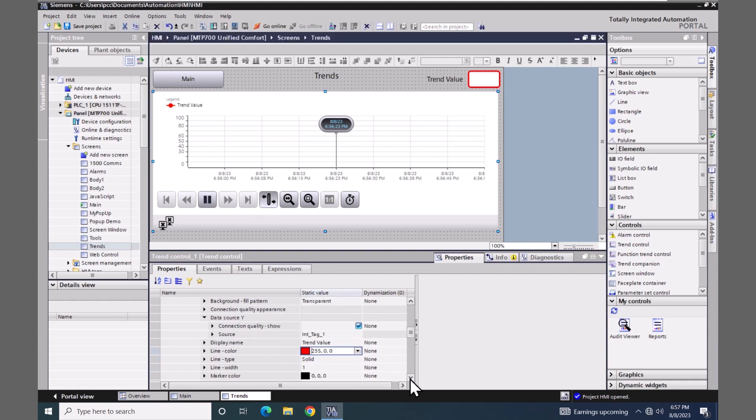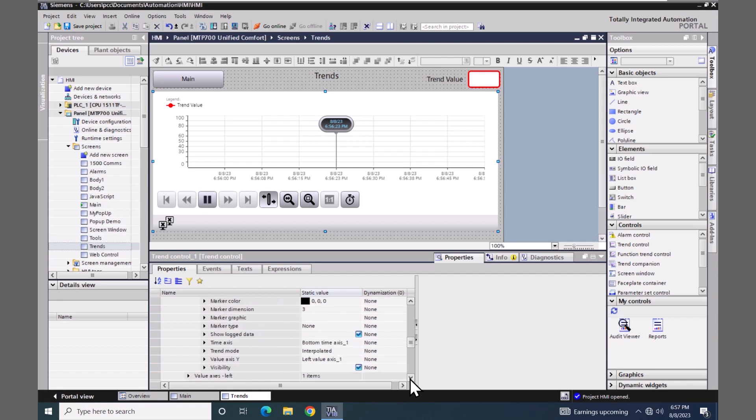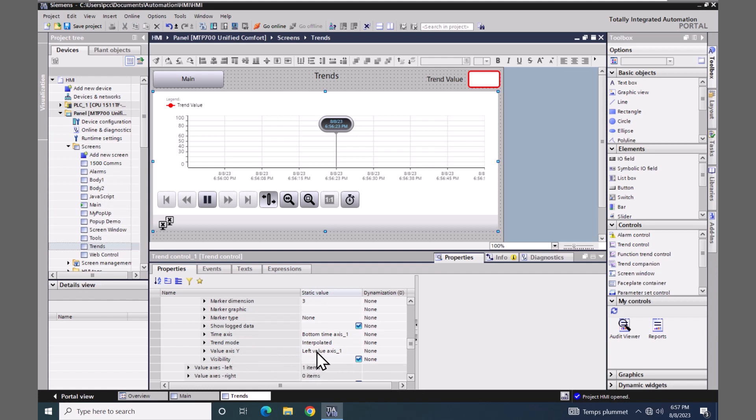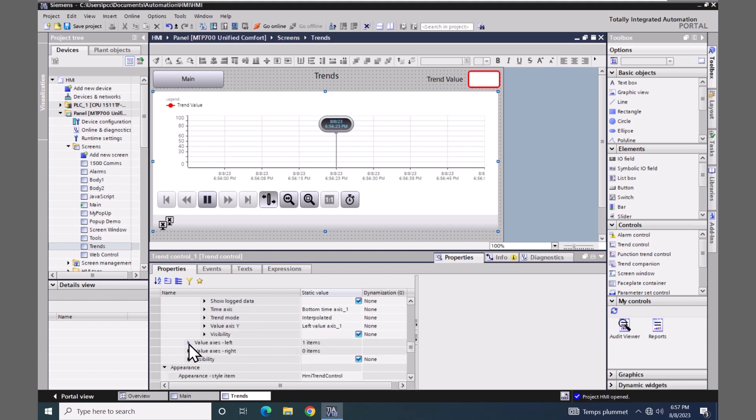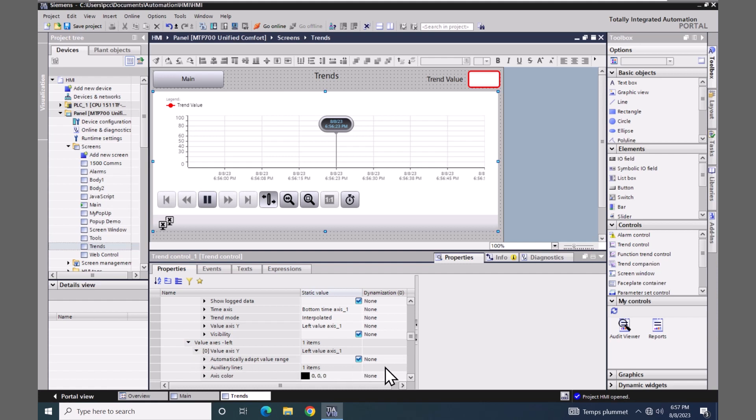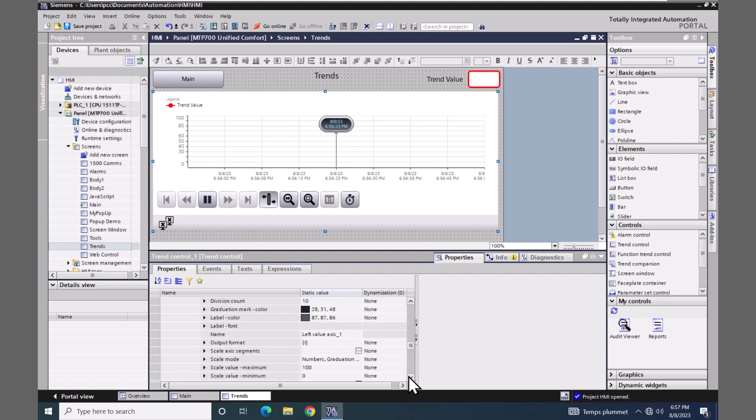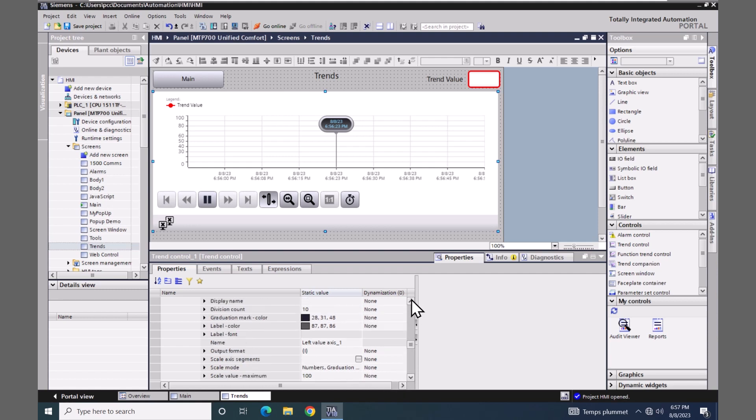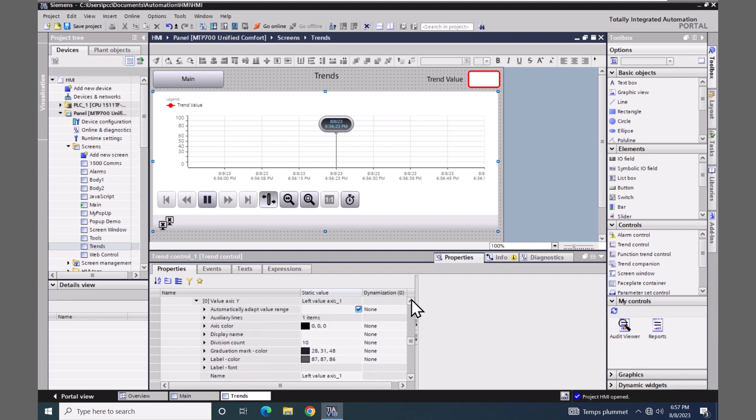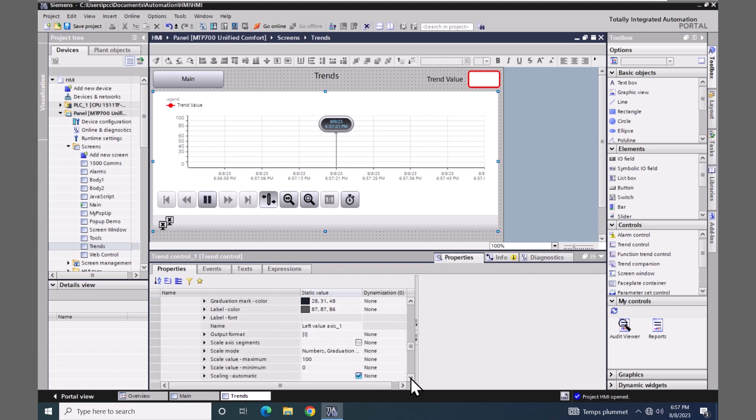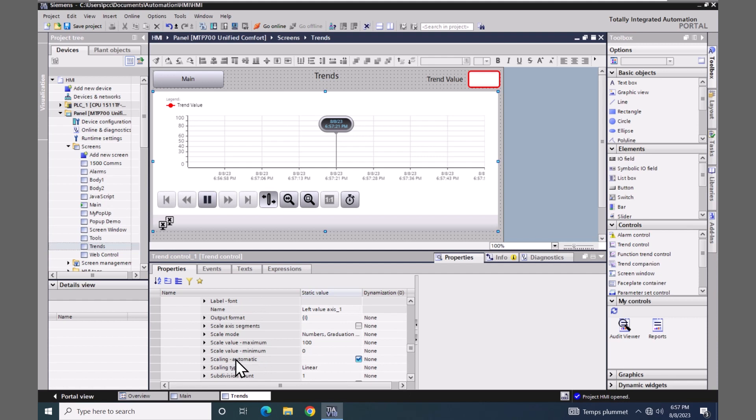I'm going to scroll down in the trend control and look at the value axis y. You can have multiple value axes configured. This one is set to the left value axis 1. So if I scroll down a little bit further I can expand out the left value axis and here is where the configuration is for this axis. This is where I can set the minimum and maximum values. So I'll say 0 to 100 is going to be my range. I'm going to uncheck automatically adapt the value range so it's going to be a fixed range. The scaling automatic, you see how not all the values are filled in here. So I'm going to uncheck this and this will fill in those values.